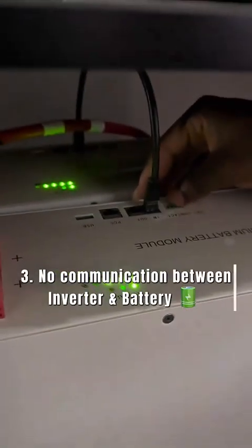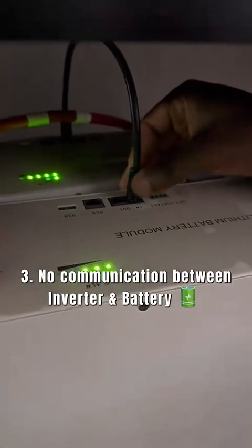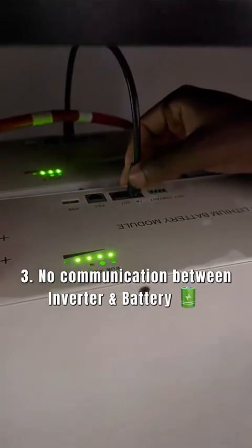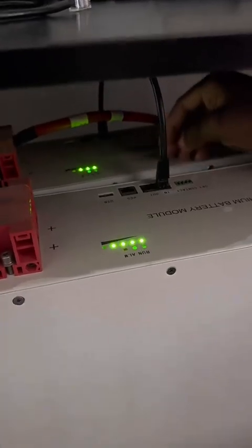Then we go to the battery. Right, so you can see that on these batteries here, there's this jumper cable, but there is no communication cable going to the inverter, which is a big problem, because these are Deye batteries on a Deye system. There's no reason for not configuring communication here. So we are going to try to configure the communication for these batteries and the inverter, so that the BMS and the inverter can communicate, which is the better thing to do.